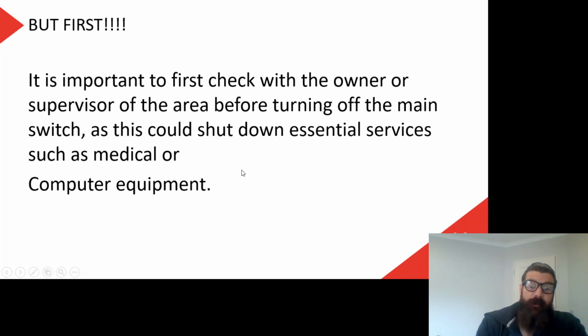First, it is important to check with the owner or supervisor of the area before turning off the main switch, as this could shut down essential services such as medical or computer equipment. So if you remember our practical book, it talks about informing first. So we're just letting whoever is responsible for that area know what we're going to do. We particularly need to do this if we're going to be switching off circuit breakers using that trial and error method to figure out which one is the one I want, because I might switch off something that shouldn't be switched off.